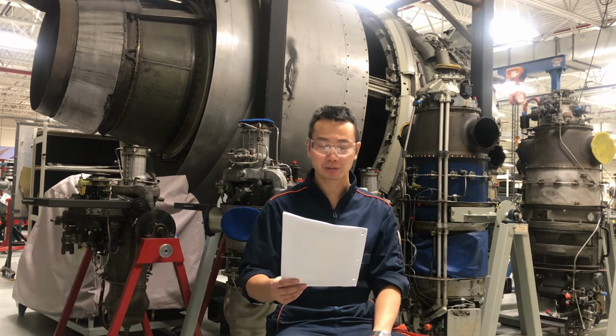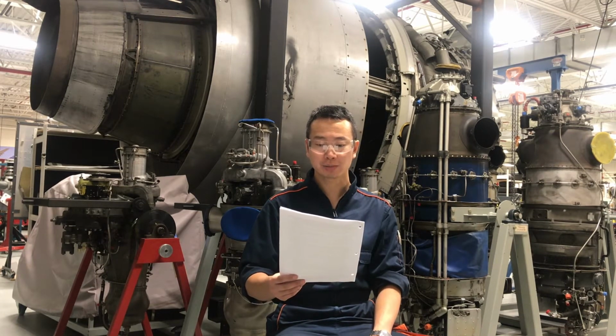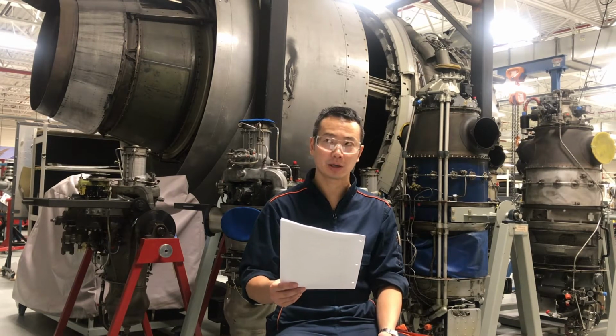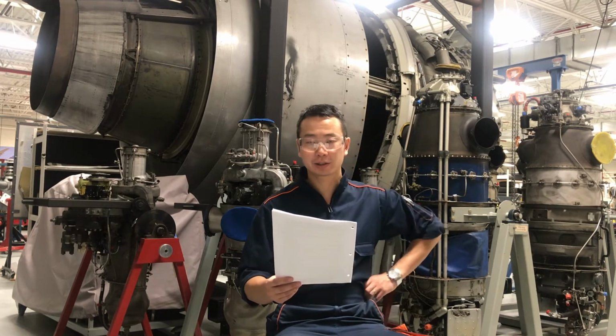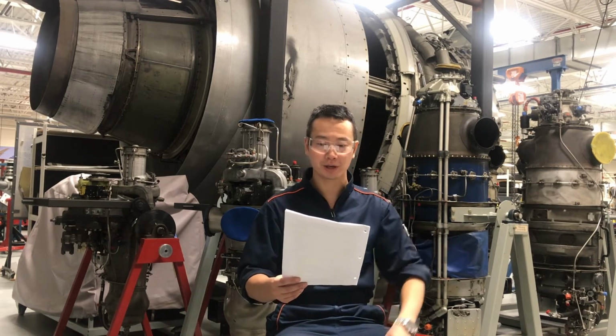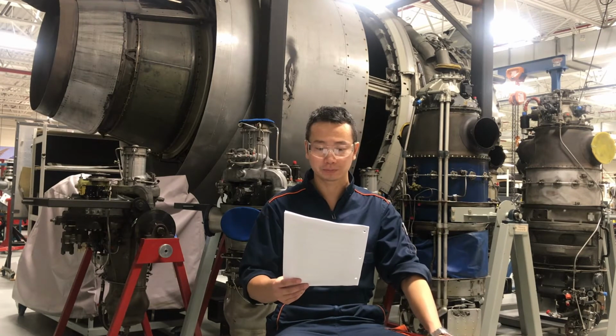And the turbine discharge pressure gauge indicates turbine discharge pressure, and this pressure needs to be corrected for the variation in temperature, compressor inlet pressure, and the altitude.